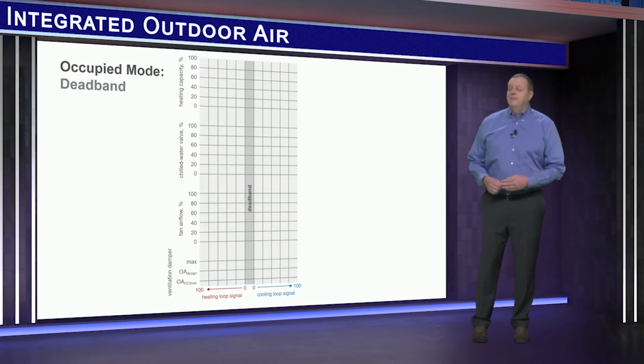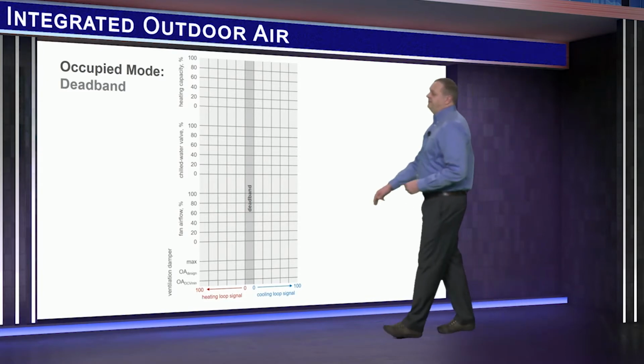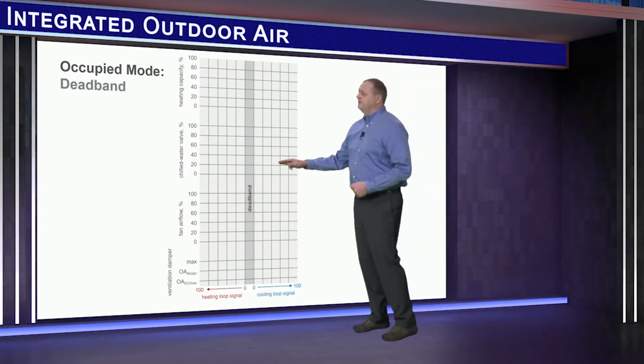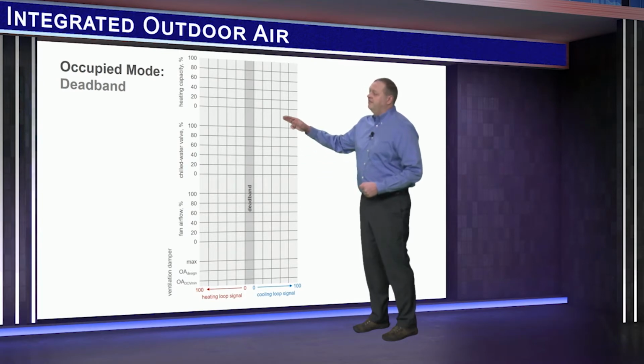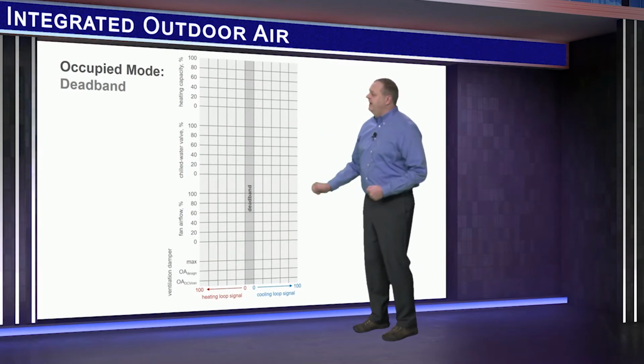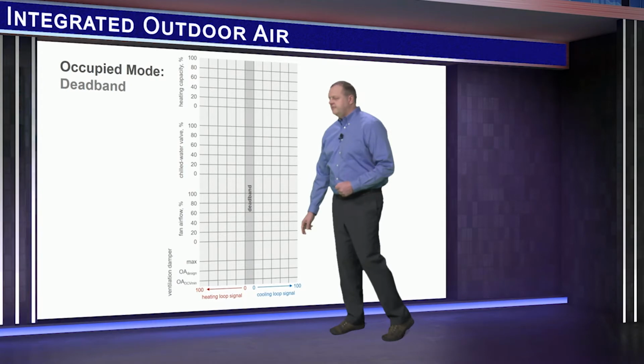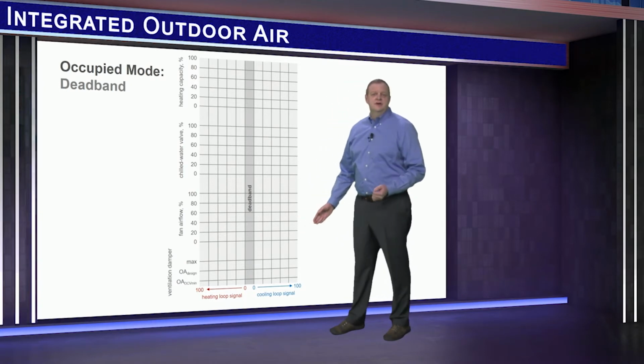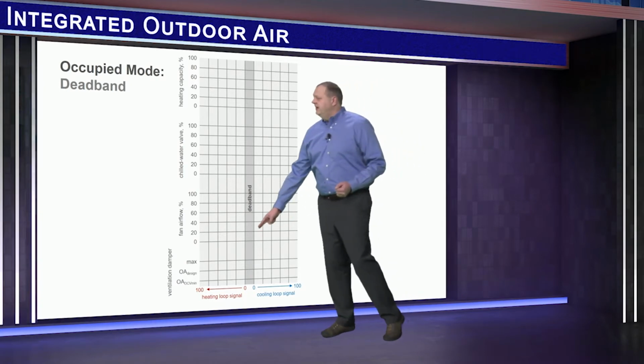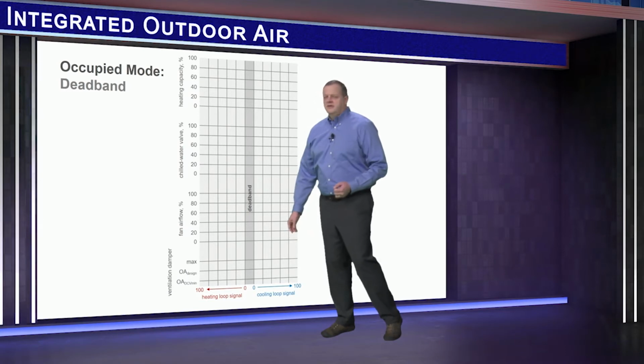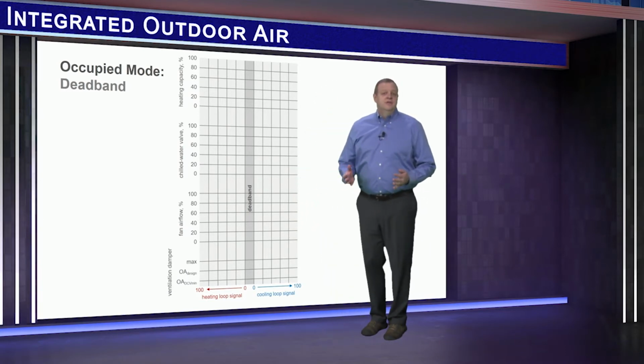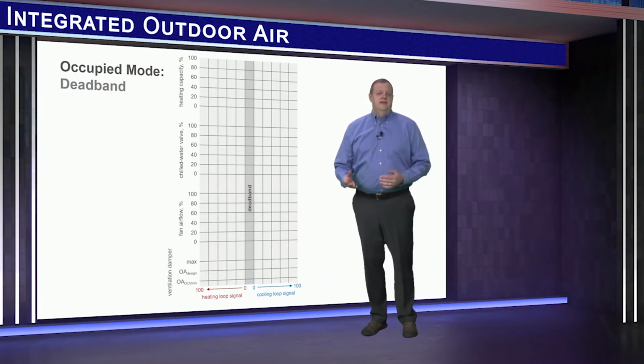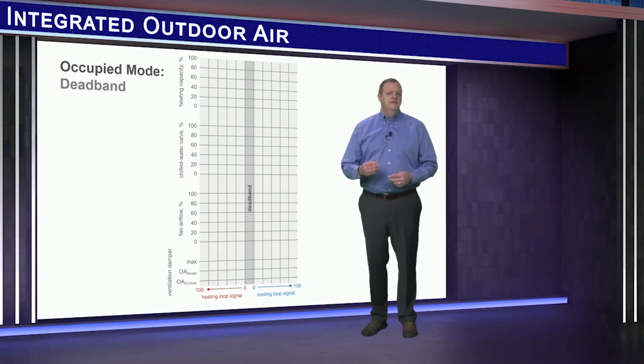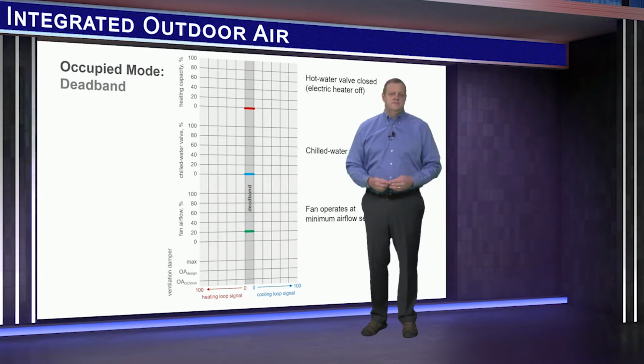This chart depicts the operation of the terminal fan, the chilled water cooling valve, hot water valve or electric heater, and the ventilation air damper. Now the x-axis is sensible load in the zone, with heating to the left and cooling to the right. So for occupied mode, let's start with the zone temperature satisfied. That is, the temperature is in the dead band between its heating and cooling set points.